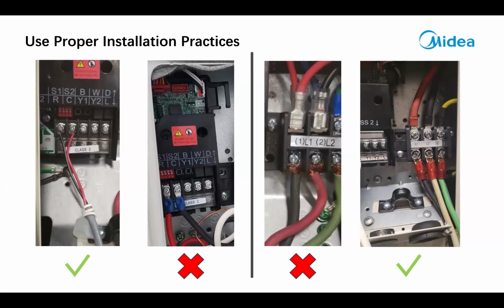If you're going to use the T screws, like I said, that T screw is actually good for anything 10 and below. You can just take the wire and put it under the terminal. If you get anything above that, you really need to have crimp-on terminals. If you don't, you're going to cause yourself some problems.